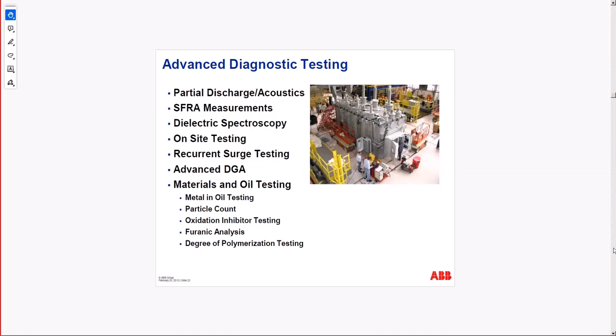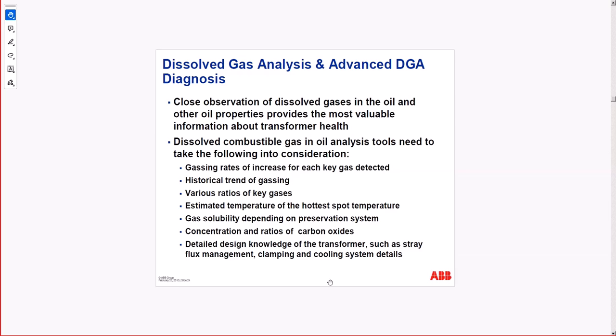So the oil, not only the gas is dissolved, we are interested in the actual strength of the oil as dielectric, and also we are interested in the oil capacity to cool and purity, so the color is also classified in the ASTM standard. We have a standard for each test. Dissolved gas analysis. So the DGA, with this slide we go into the DGA, gas rates increase for key gas detection, history of the, you need to trend, and you need to see per each gas what is the value, how close you are to the limit. And then for some methods, like Rogers method, is actually using the ratio of different gases, not the actual value of the gas. And the other thing is the rate of change.